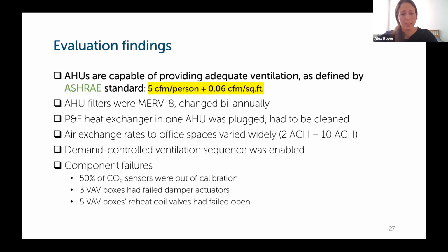Then the testing and balancing contractor's results showed that air exchange rates to the office spaces varied widely from 2 air changes to 10 air changes per hour. So we want to even those out in the various zones in the building, and that's to ensure that everyone's breathing zone has been filtered and ventilated properly.